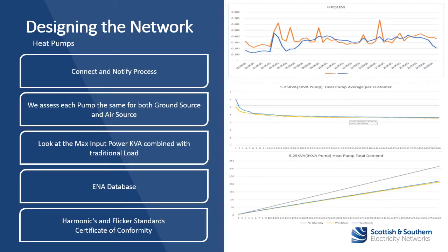If we look at the heat pump process, the ENA has developed some very good processes, and they continue to develop good processes for heat pumps. There's actually a process where you can connect and notify as long as your installation meets the criteria: so long as the cutouts and the fuse are the right size, so long as the site demand is quite low, and so long as the heat pump falls under the connect and notify process. This means there won't be any network studies and there's no work to do. You just connect it and notify us that you've connected it.